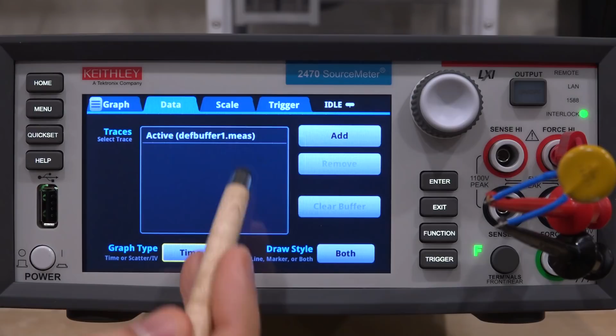Over here, the current is limited. So this is now time, not voltage. So the voltage has been decreasing down to 750 volts negative, but it's being kept constant by the current limit of this unit. And then once we pass the trigger point of the Varistor, we come back to 0, and then on the other side, symmetrically the same way.